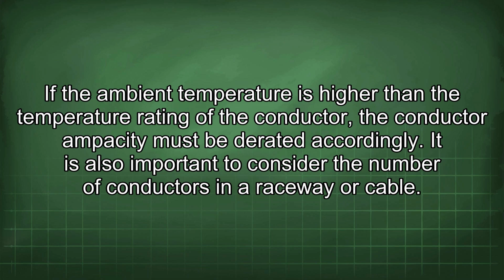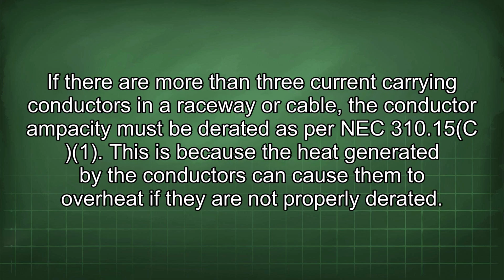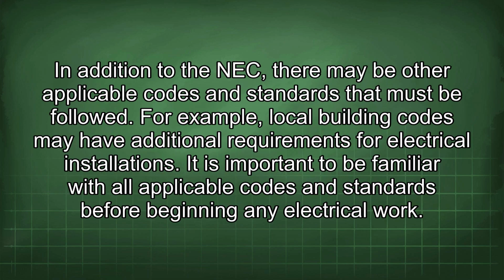It is also important to consider the number of conductors in a raceway or cable. If there are more than 3 current-carrying conductors in a raceway or cable, the conductor ampacity must be derated as per NEC 310.15. This is because the heat generated by the conductors can cause them to overheat if they are not properly derated.